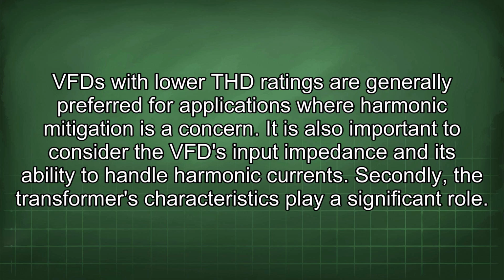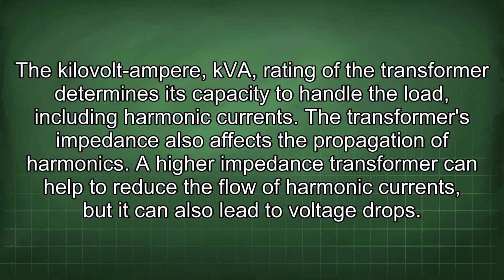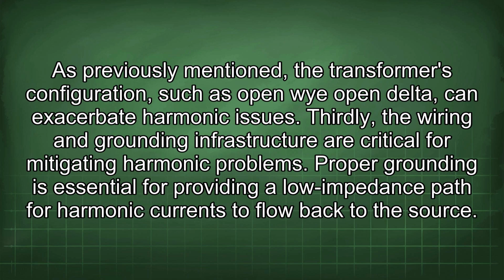Secondly, the transformer's characteristics play a significant role. The kilovolt-ampere (kVA) rating of the transformer determines its capacity to handle the load, including harmonic currents. The transformer's impedance also affects the propagation of harmonics. A higher impedance transformer can help to reduce the flow of harmonic currents, but it can also lead to voltage drops. As previously mentioned, the transformer's configuration, such as open Y-open delta, can exacerbate harmonic issues.